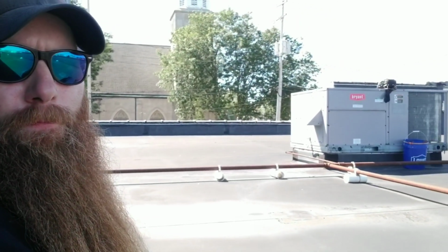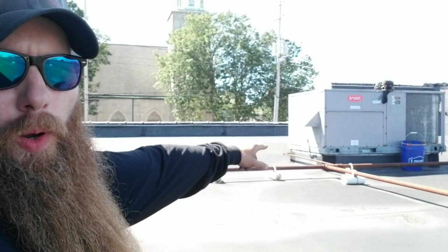Alright guys, we're wrapping up this call here. That's our unit right there that we were working on. And as you've seen, we had a faulty switching relay that was internally melted, which had caused our breaker to trip. You didn't see it on camera, but I did go ahead and replace that relay with a spare that I had. Our final supply temp was 54, our return was about 76, so we had a good 22-degree split on there.